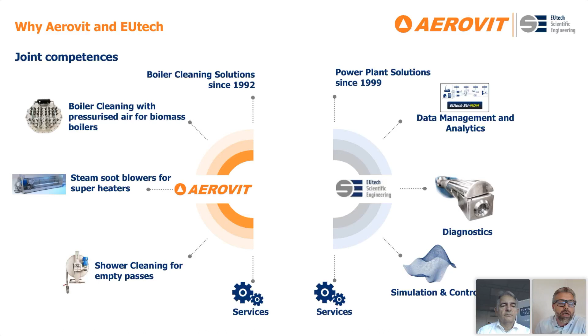We have boiler cleaning solutions using pressurized air, sending shock waves into fire tube boilers, catalysts, or economizers. We can also supply steam soot blowers for larger boilers and superheaters. But what we'll talk about more today is shower cleaning for the empty passes on different kinds of fuel — waste energy, biomass, coal, and so on. We always strive for a very high level of service and good quality.